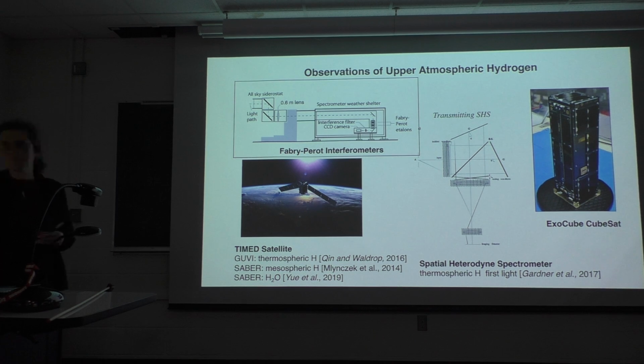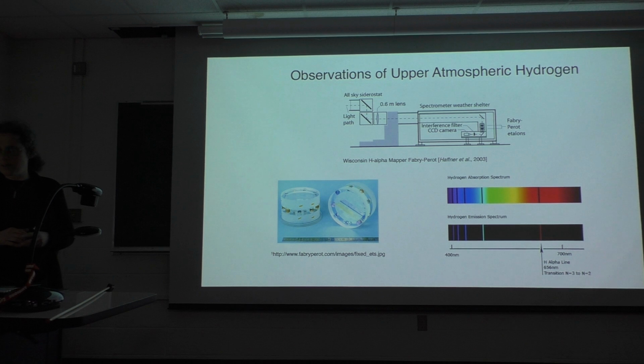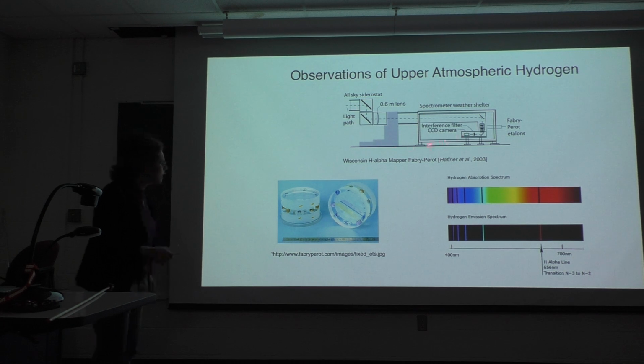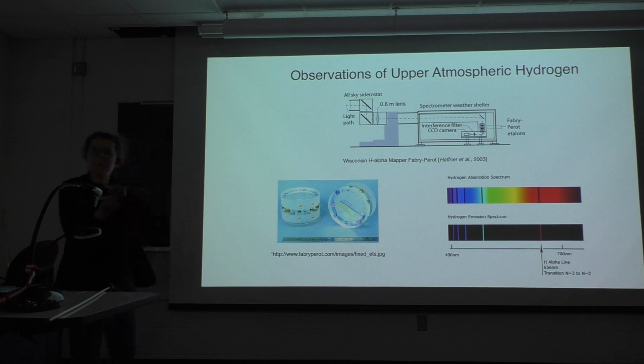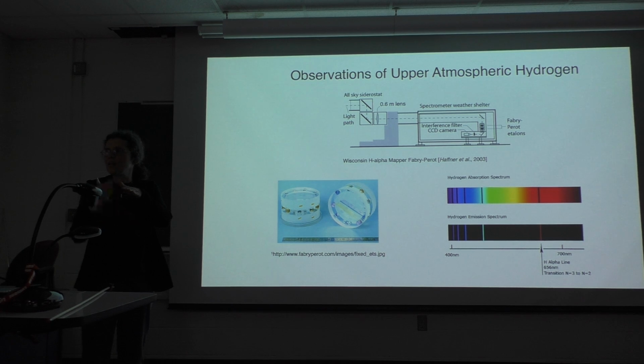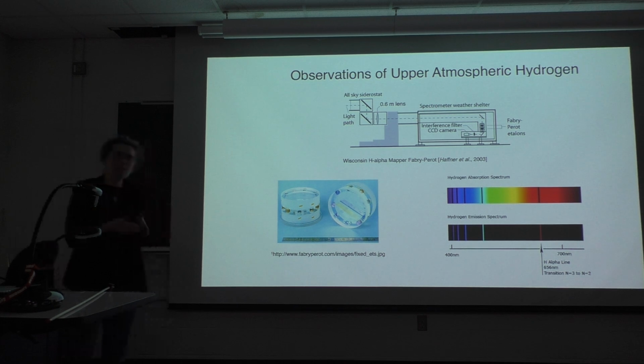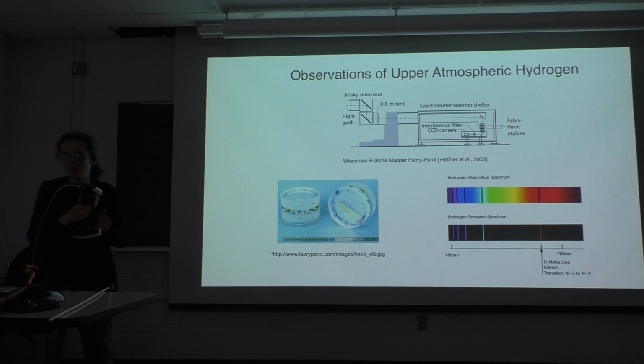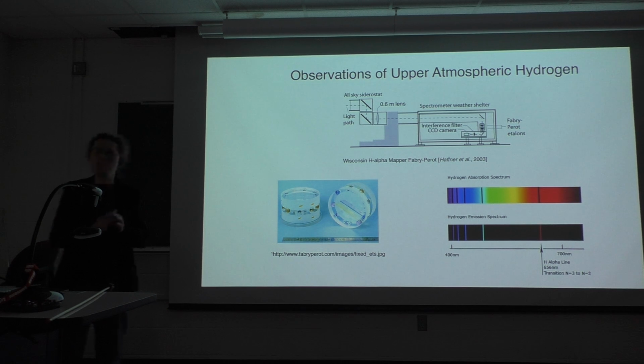But today I'll focus on the Fabry-Perot and mention a bit about how the measurements are made and the instrumentation. So this is a Fabry-Perot spectrometer. The core of the spectrometer are etalons, very flat plates of glass, and light can reflect multiple times between the plates of glass, thereby producing a very narrow band interference, because you have multiple passes interfering with one another. So you're able to produce a very narrow, high resolution measurement.